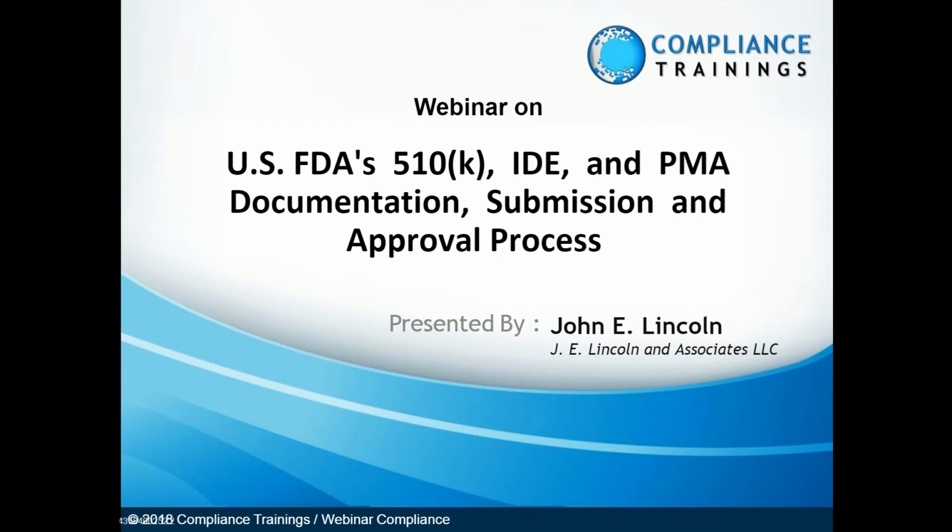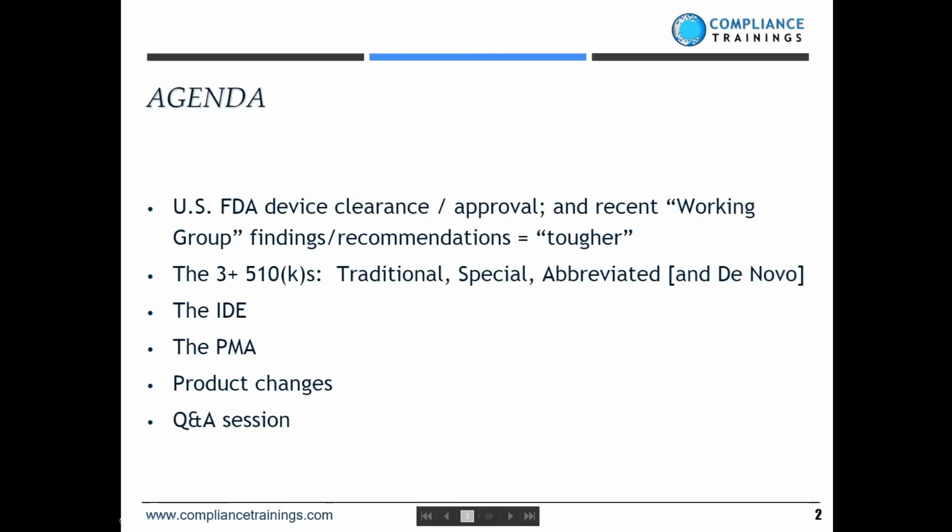So the more I can show them a rationale and a submission, a bit of information that's concrete in the form of an IDE copy, a hard copy, then I can get better feedback from them. So just bear that in mind. That's kind of the caution I would recommend when you're dealing with the FDA. Just like any person getting a phone call, you yourself are going to be very cautious because you don't want something taken out of context later on, and someone says, well, they said I could do this type of thing.